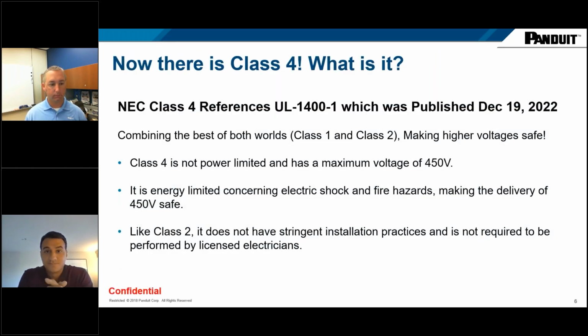Now there's Class 4, and NEC Class 4 references a new standard, as Frank was talking. It came out by UL, published last December. It's UL 1400-1. It's referred to as fault managed power. You'll hear so many different names around this new technology, but the best way for me to describe it is combining the best of both worlds, classes 1 and 2, where you're making the delivery of high voltages safe.